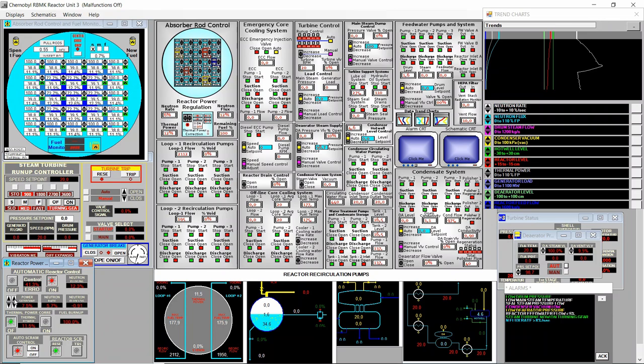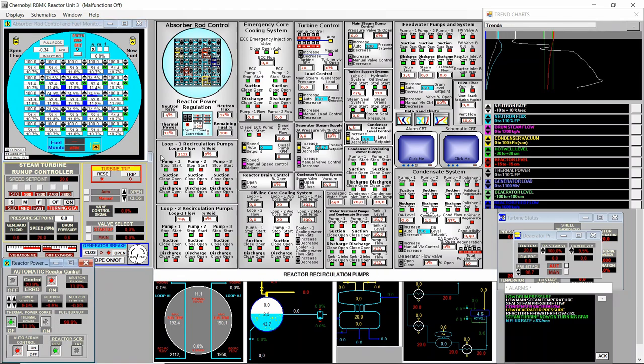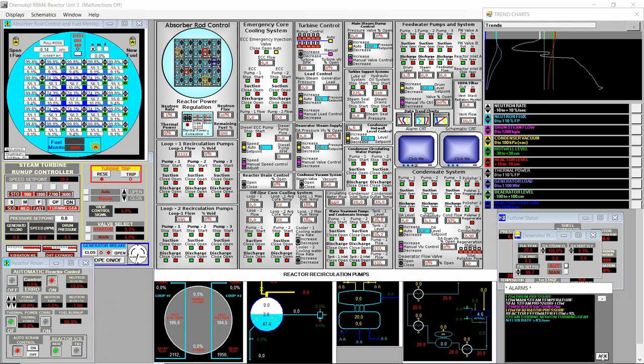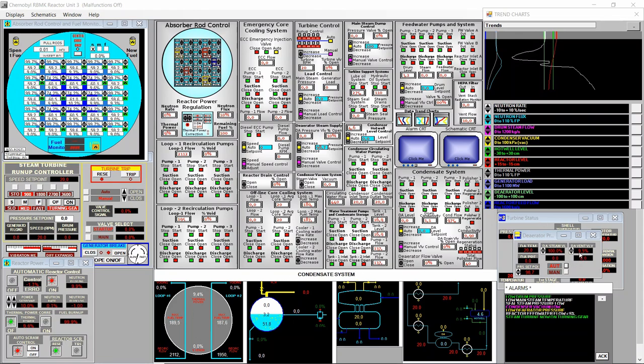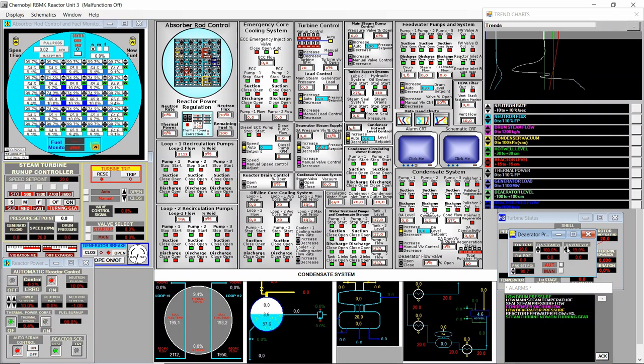We have a neutron flux of 12 percent — that's not normal. The automatic control wasn't engaging because we were in center core only; we need to be in full core. Now it engages and tries to reduce the neutron flux to nine percent. I acknowledge all the messages. While everything heats up, I increase the deaerator vent valve to 50 percent.